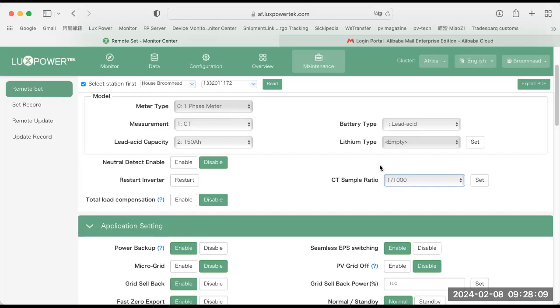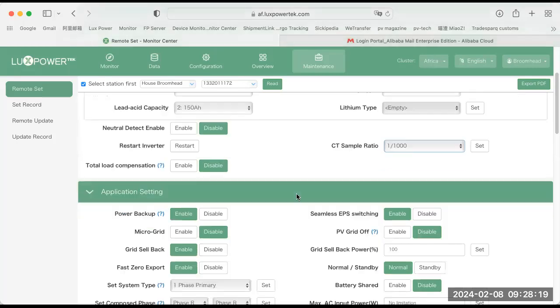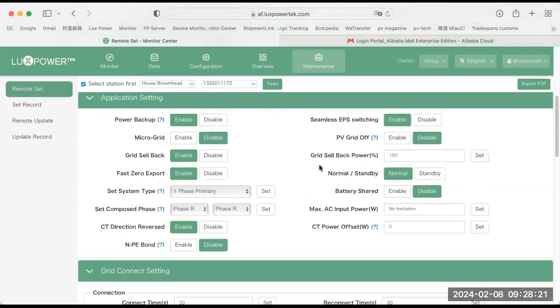So, for instance, you might have your sampling point 100 meters away from the machine itself, and you're going to put in a different CT. Then typically we would go to a 1 in 3,000 sample. All right. On the application setting here, just remember that power backup, you have to enable this, because if you do not enable it, it simply means that if you hold the cursor over the question mark here, it simply means that the EPS output will be interrupted.